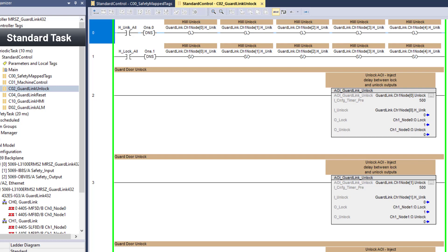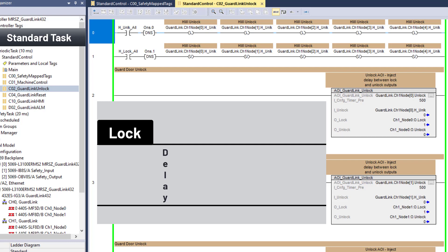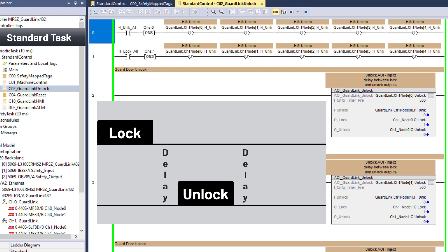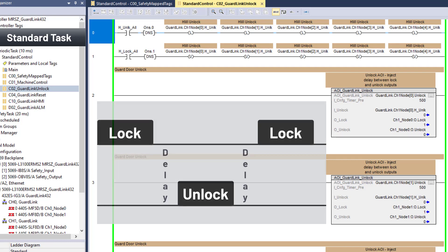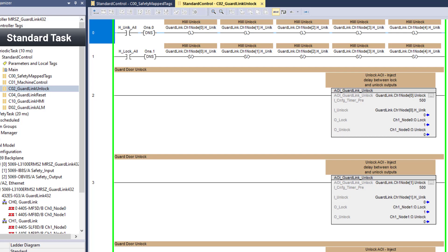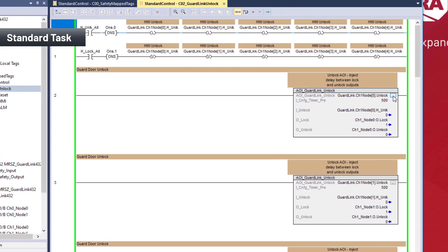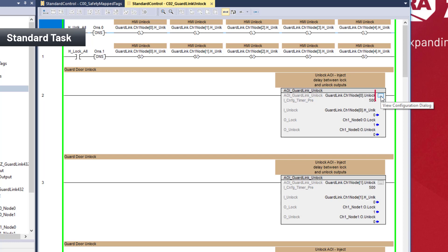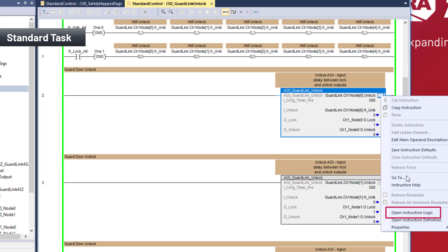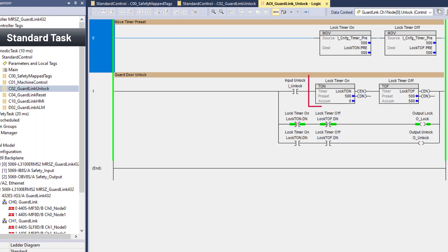To satisfy GuardLink, there must be a delay between the removal of the lock signal and energizing the unlock signal. There must also be a delay when locking. A simple add-on instruction was developed to inject a configurable timer preset between the lock and unlock outputs. To see the logic, right-click on the AOI and select Open Instruction Logic. The add-on instruction consists of two timers that separate the lock and unlock signals. Close the AOI logic.